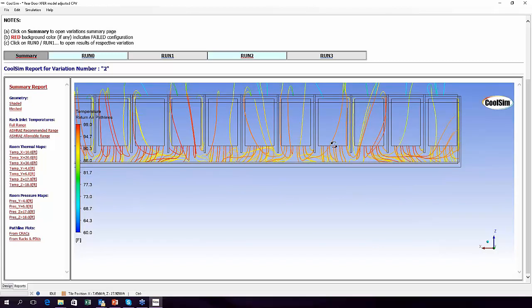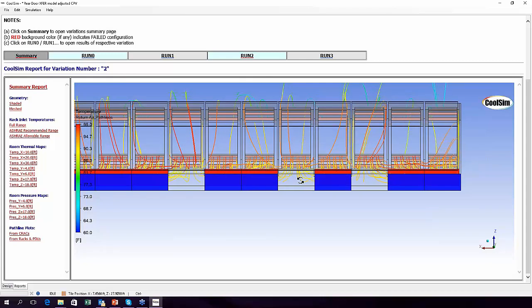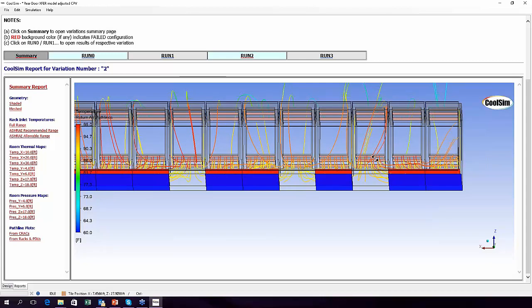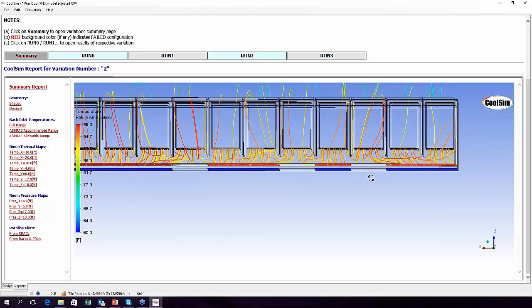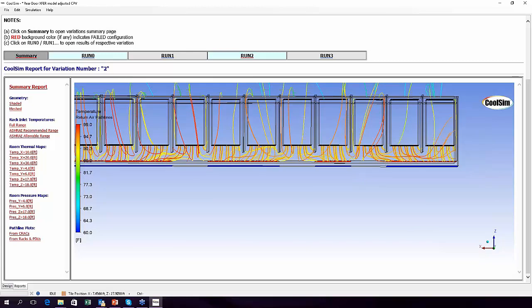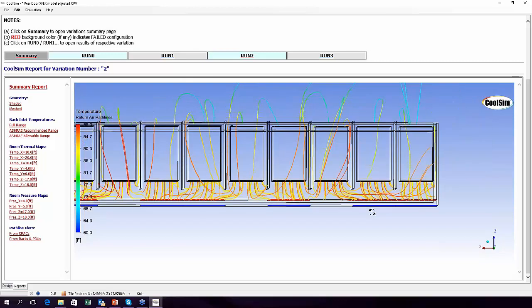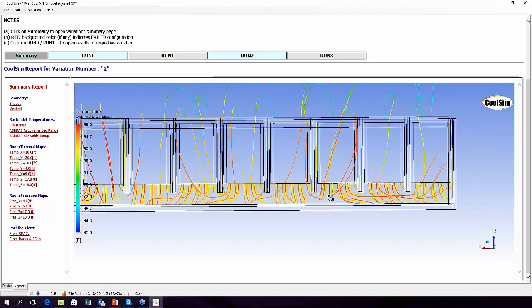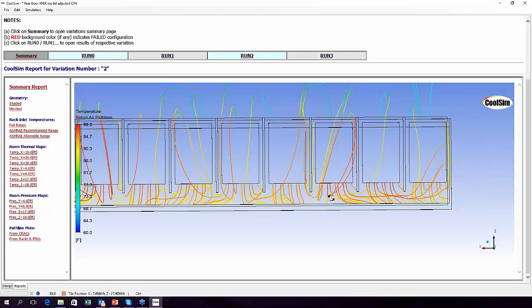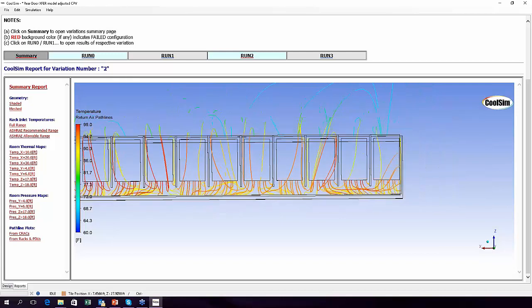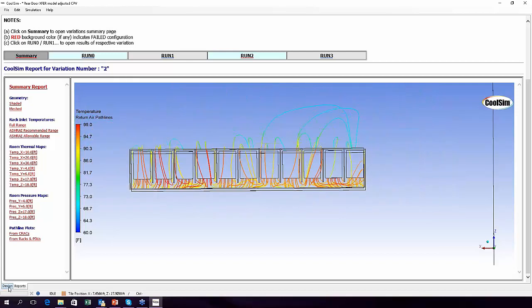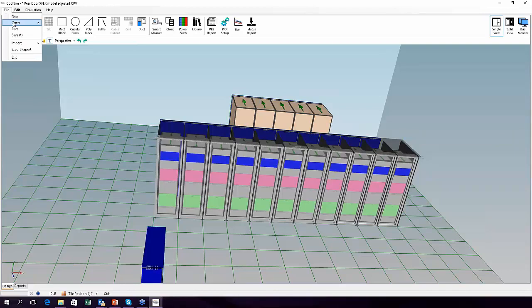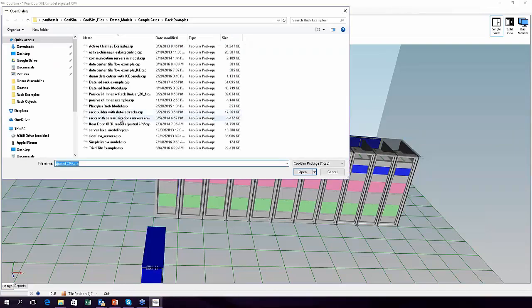In other words, the unit behind here, I think, has failed right there. So its hot air can go over and pass through this one because we don't have a block going all the way back. In reality, they do. There's usually one of these per cabinet, and there's no opportunity for one to cover for the other. And so it wraps. But yeah, rear door heat exchanger is not a problem. We can model those as well. Let's see what else we have here before we start to move on.